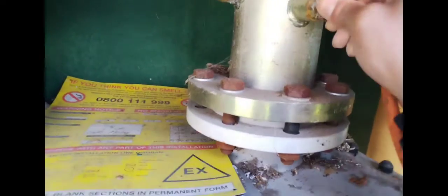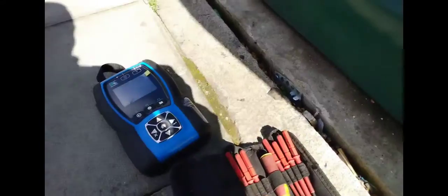So I'm connecting my gauge. Ideally we want 20 or 21 millibar in this scenario. Just going to wait for it to stabilize. Also check your conditions — make sure you've got the right weather conditions when you are testing. I'm using my number here; my 160 — sometimes people can see the 100 and get confused. My manometer is stabilizing around about 23. I've carried out my tightness test and it is successful — I didn't really have any drop whatsoever — so I'm opening back up my valve.